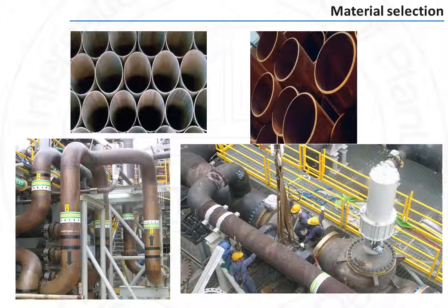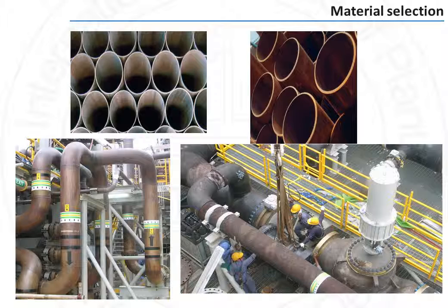The selection of the material of construction depends on the type of fluid handled, its corrosiveness, its pressure, and its temperature. Looking first at pressure, the pressure of the carried fluid will induce the strength requirement of the material of construction. For high pressure, high strength material will be selected to reduce the wall thickness.